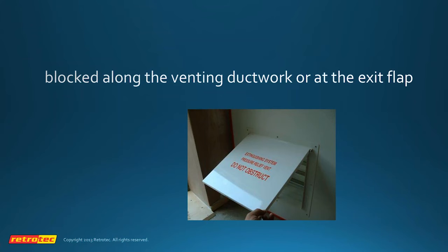When you do the door fan test of the enclosure, you're doing two door fan tests. One door fan test you're using to discover the hold time. And in that case, you don't want to cover your pressure relief vents, but you want to stop them from moving. The actual pressure during the hold time will only be about 4, 5, maybe 10 pascals maximum on these vents. So when we measure the leakage of the room, we actually take the room up to 50 pascals, which might be capable of moving your pressure relief vent.